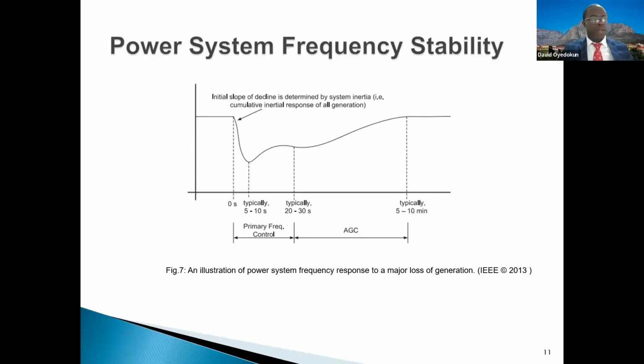Sure, I'll take it and go back to the figure I had earlier. At the point of a contingency — for example a large loss of load or a large power station coming online — if at that instant you have a significantly higher level of load compared to generation, you'll have an under frequency situation. Typically the governors at power stations participating in primary frequency control, as mentioned earlier, will respond to try to balance out the frequency deficit. Then secondary and tertiary frequency control kicks in, with tertiary moving into economic dispatch, which is a slightly longer horizon.